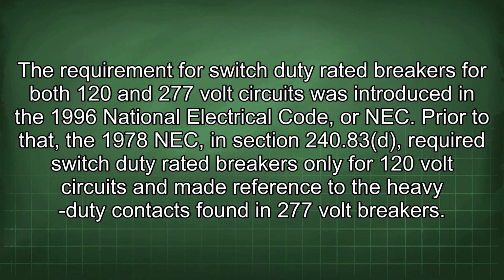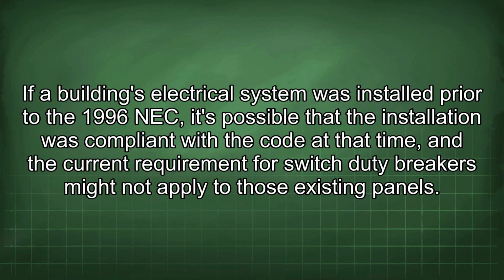The requirement for switch duty rated breakers for both 120 and 277 volt circuits was introduced in the 1996 National Electrical Code, or NEC. Prior to that, the 1978 NEC in section 240.83 required switch duty rated breakers only for 120 volt circuits and made reference to the heavy duty contacts found in 277 volt breakers. If a building's electrical system was installed prior to the 1996 NEC, it's possible that the installation was compliant with the code at that time, and the current requirement for switch duty breakers might not apply to those existing panels.